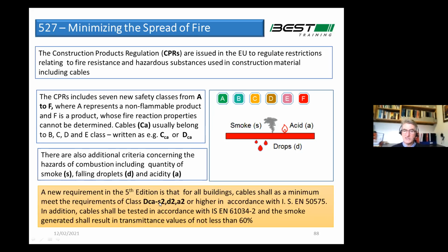That's all that means. And then the 3 other references are S2D2A2. So S stands for smoke, D stands for droplets, and A stands for acidity. So you're looking at the hazardous nature of the cable when it's burning, when it's attacked by fire, what happens. So we're looking for obviously minimal smoke, minimal acid, and minimal drops from the cable. So S2D2A2 is the particular specification we went for. For example, S1 is better than S2, D1 is better than D2, and A1 is obviously better than A2 as well. So a lot of people are now calling in their specs for cables to meet CCA classification. And there's no great difficulty in getting these cables. People thought at the start, oh God, this is something unique to Ireland. It's not, we're only 1% of the population of Europe, and with these wiring rules, everyone's basically specifying similar cables throughout Europe.